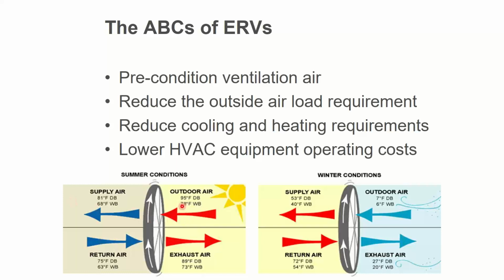You'll also notice I'm also drying it out. I'm dropping it from 78 wet bulb to 68 wet bulb because some of this moisture also went into this side of the heat exchanger. So heat and moisture both go this way and get exhausted out, leaving me with cooler, not cool, but cooler and drier air.